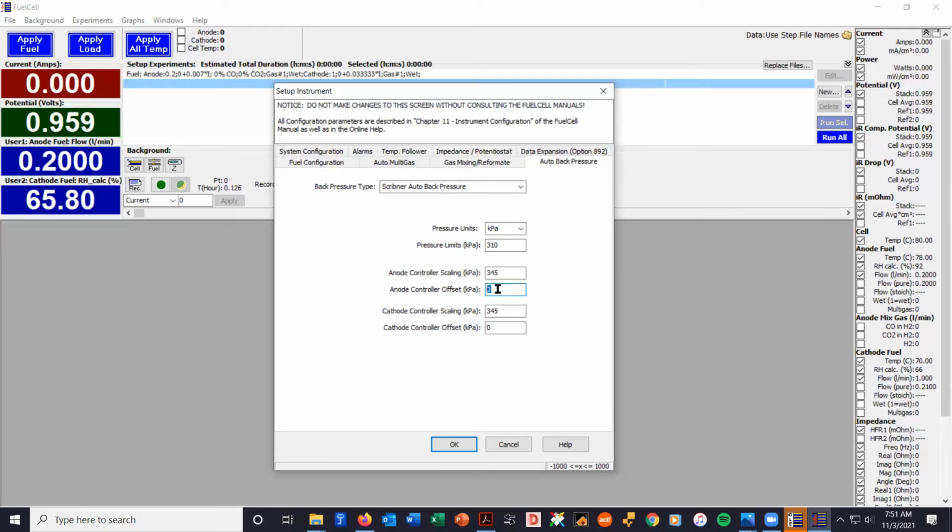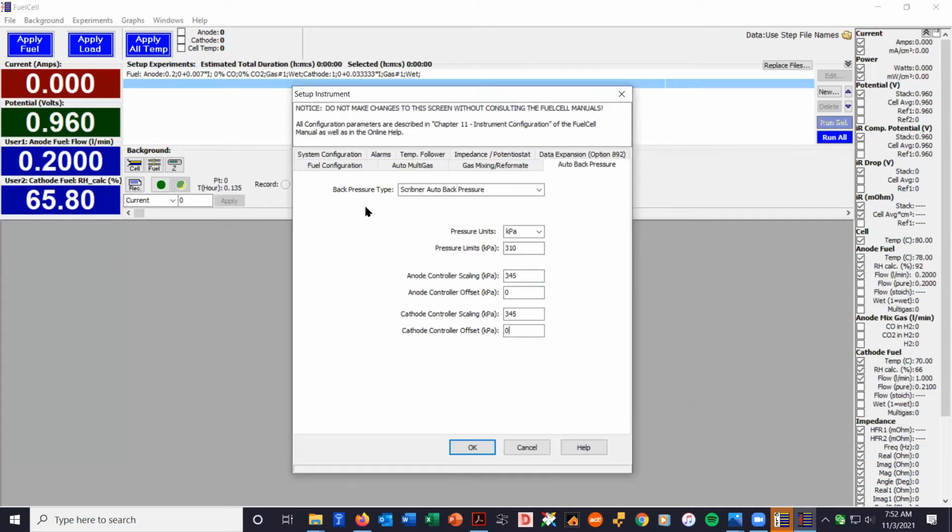During the configuration and installation of the auto BP unit, we ask that the customer enter those offset values. If they're left at 0, it's not typically a big deal, because the offset is a very small value, somewhere between -2 or 3 and +2 or 3. So we're talking about just 1 or 2 kPa anyway. It's not generally a big factor, but it is there. And that's pretty much it.